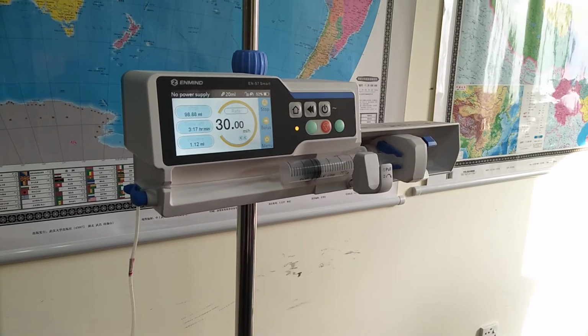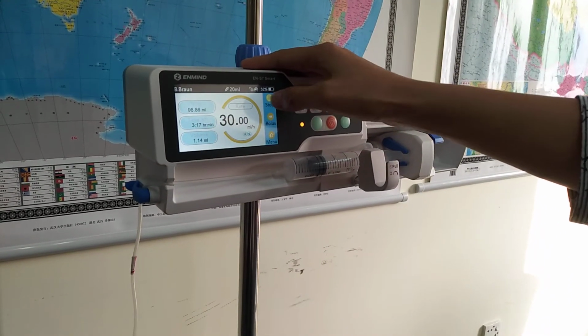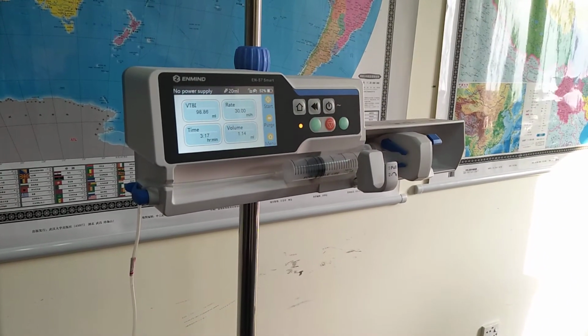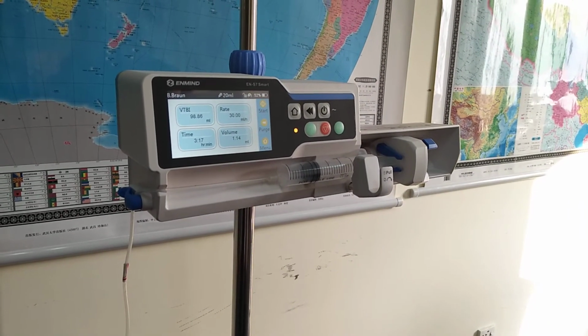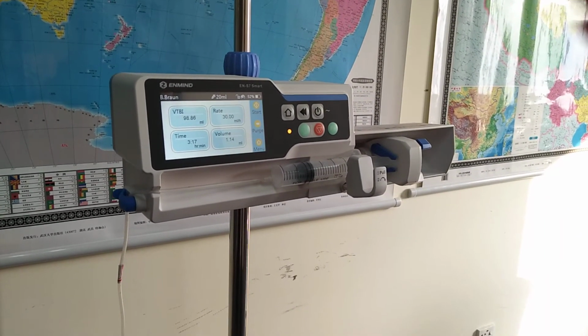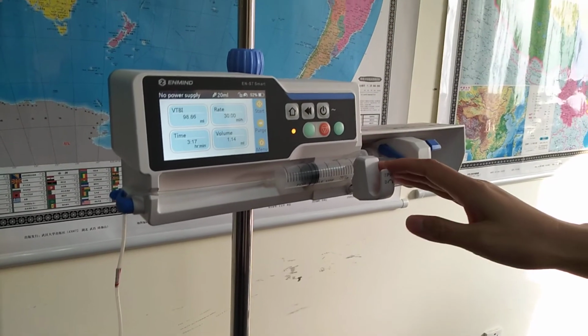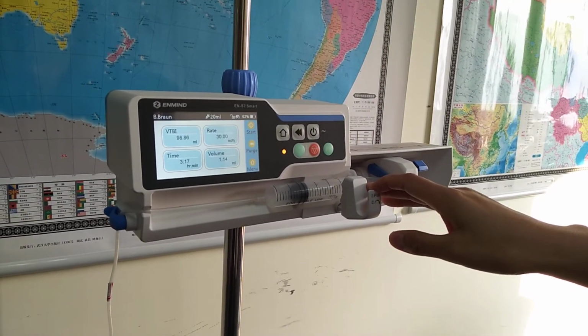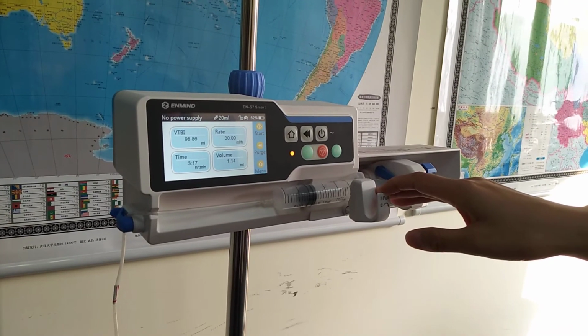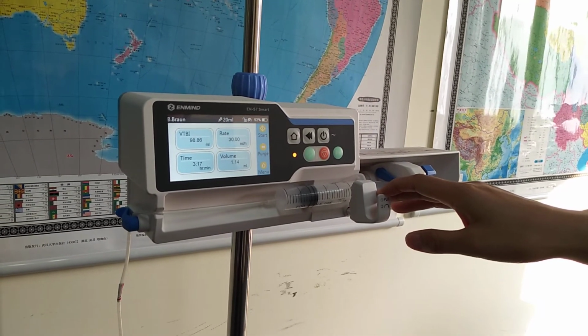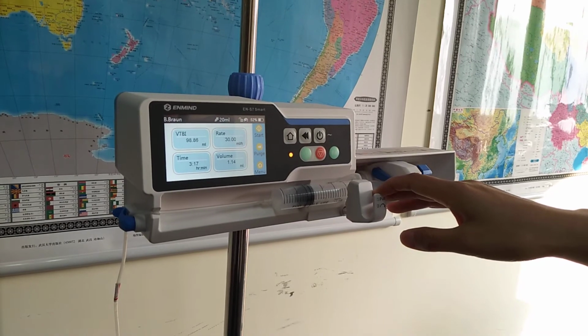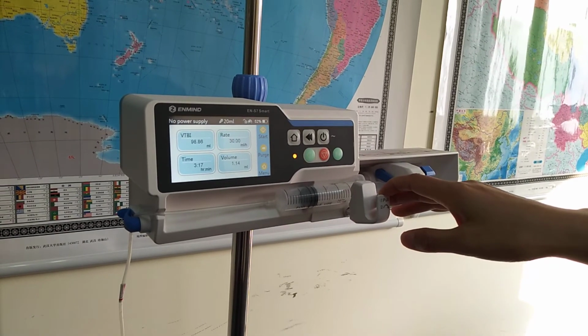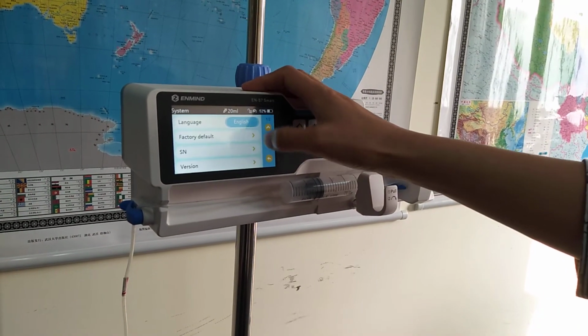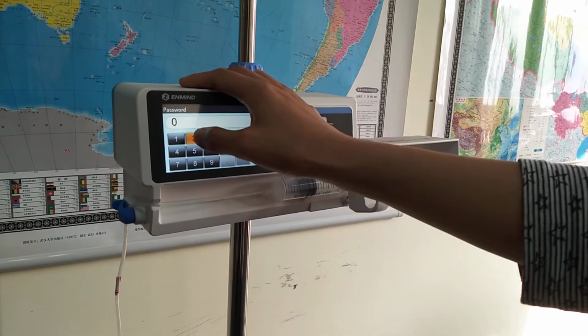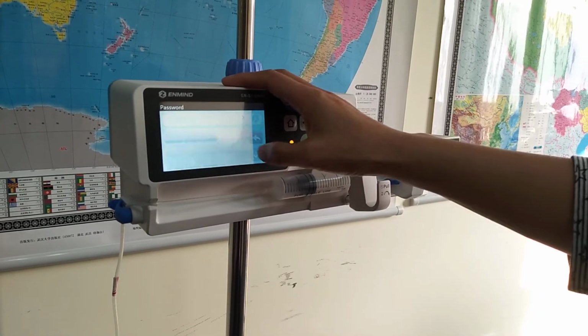Now we will show how to do the calibration. So we stop it first. Please make sure you have the following items when you do the calibration: syringe pump, syringes. When it's your first time to use a pump, or when a new brand needs to be added, or when the accuracy is not good, you need to do the calibration. So go to the menu, System, Maintenance with password 2341.